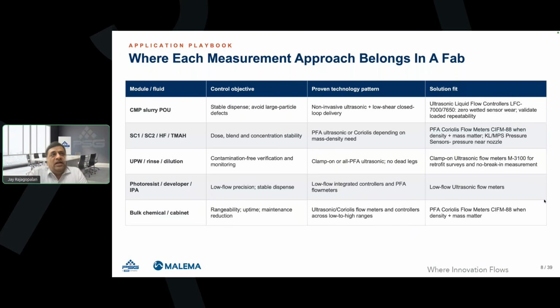For the ultra pure water, contamination free is the control objective. So there, a non-obstructive flow path or clamp-on devices are usually preferred. For photoresist or other coated applications, spin-on dielectric, etc., a low flow precision is required, extremely low dosage. The volumes could be in microliters, in which case low flow ultrasonic flow meters can be applied. In bulk chemistry or chemical blending applications, rangeability, uptime, and maintenance reduction are obviously preferred. In this case, both ultrasonic and Coriolis technologies can be applied. With that, let's go into the application-specific case studies and areas of discussion.